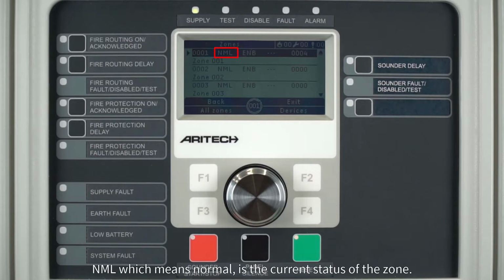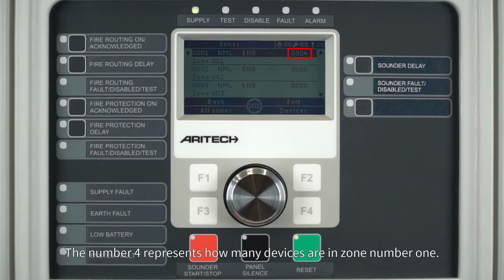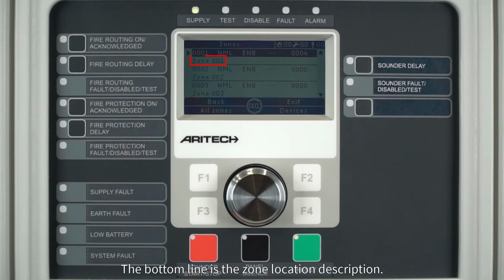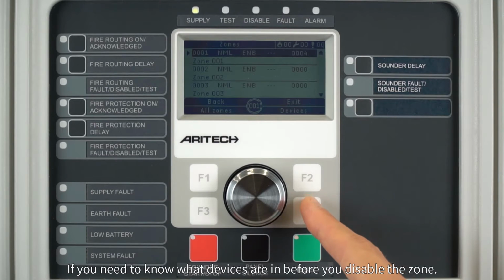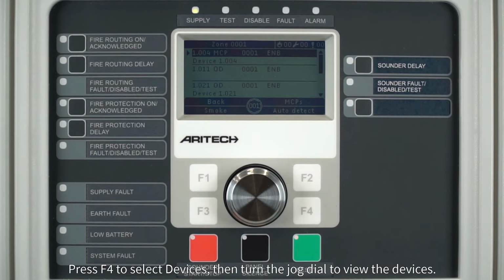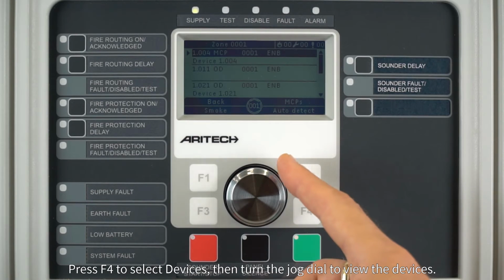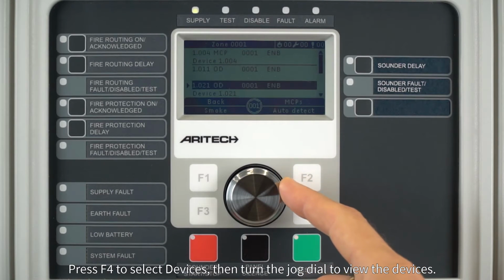NML, which means normal, is the current status of the zone. ENB means that the zone is currently enabled. The number 4 represents how many devices are in zone number 1. The bottom line is the zone location description. If you need to know what devices are in before you disable the zone, press F4 to select devices, then turn the jog dial to view the devices.